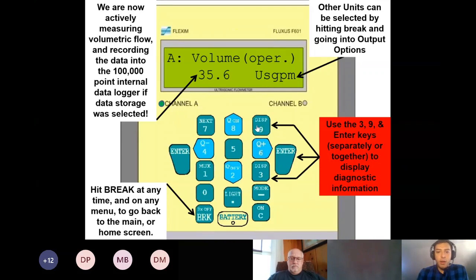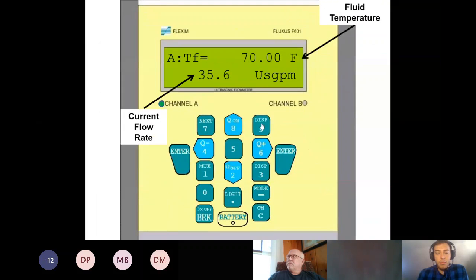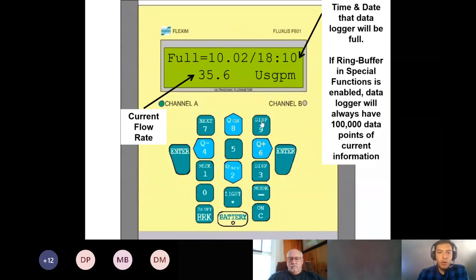That's on the bottom. If you want to change the bottom display, you would hit this 3 button. You see it says DISP on the top. This is changing the bottom display. And then the 9 changes the top display. So for the top displays, you have your fluid temperature. This is the date and the time that the data logger will be full. It is in European format, so this is actually February 10th.